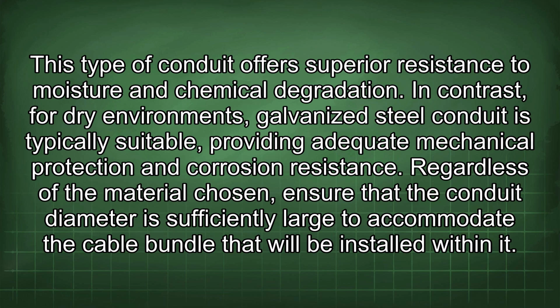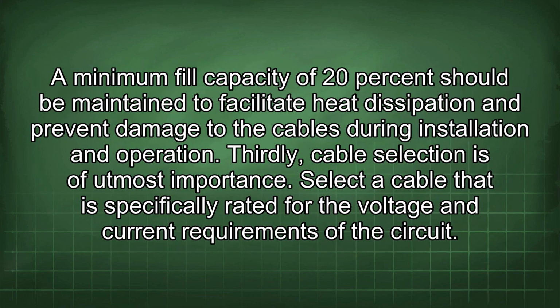Regardless of the material chosen, ensure that the conduit diameter is sufficiently large to accommodate the cable bundle that will be installed within it. A minimum fill capacity of 20% should be maintained to facilitate heat dissipation and prevent damage to the cables during installation and operation.